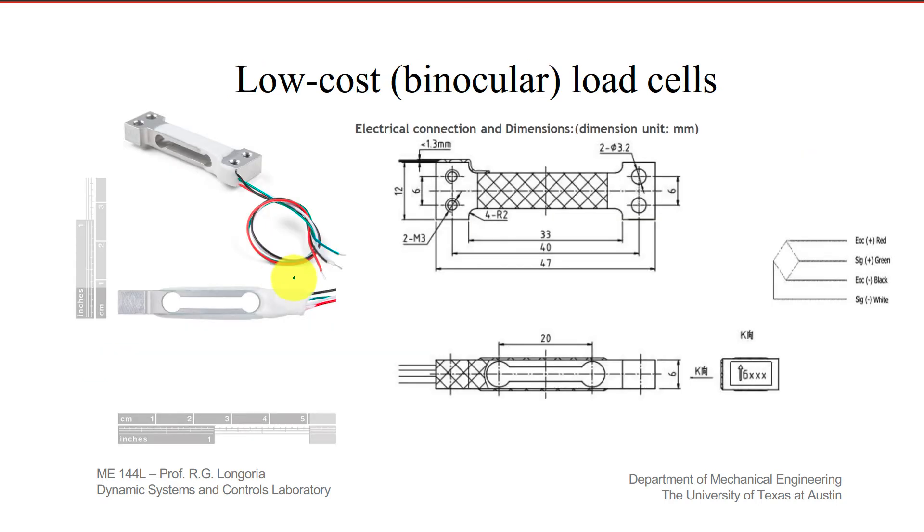And so here's the low cost binocular load. You can find some high grade ones, and this one that I found was only about $10. So I wanted to use a low cost one to see how well they'd work. As you can see, it's got that binocular design, and here are the dimensions in millimeters. And you can see the spec page from the manufacturer, it's configured as a Wheatstone bridge. You've got four gauges on here. I'll show you a little bit more information on this.